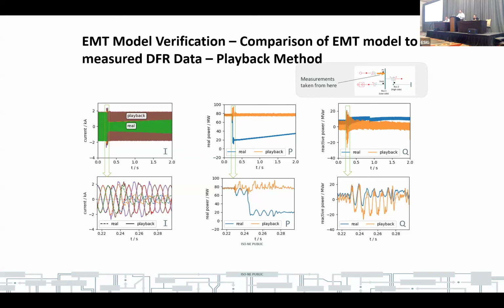There was a substation a few substations away from this plant specifically, and there was low SF6 on one of the breakers, so there was a bus trip at that station. However, at this plant, there was really only a 10% voltage deviation, and it was actually over the course of about 5 seconds. So it was relatively small and relatively long duration.